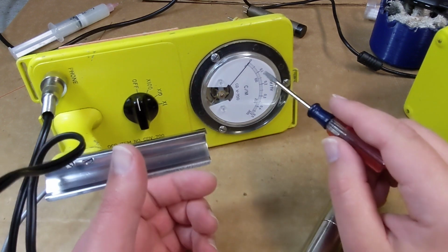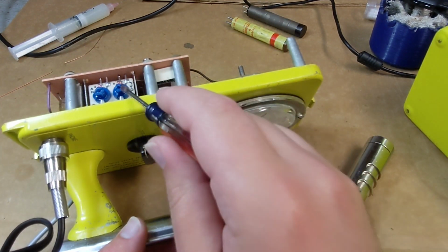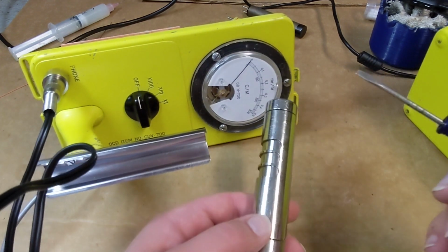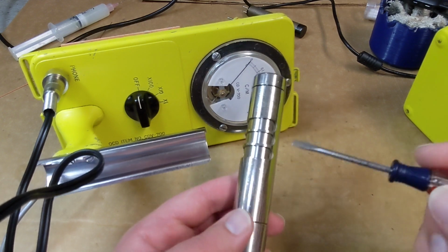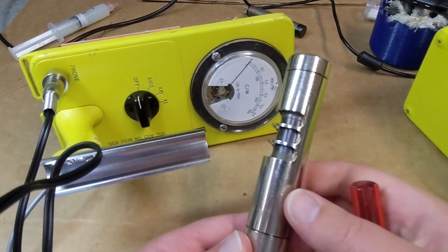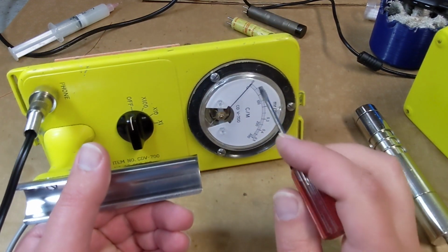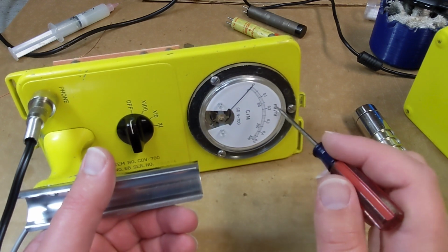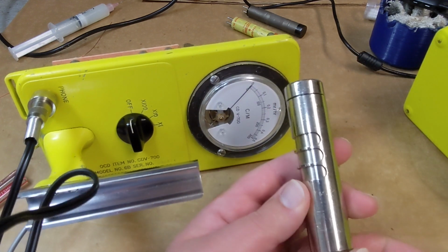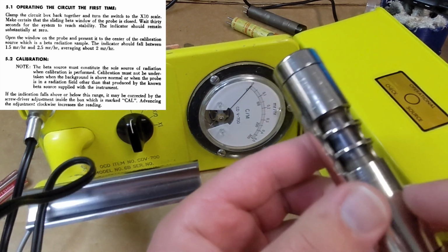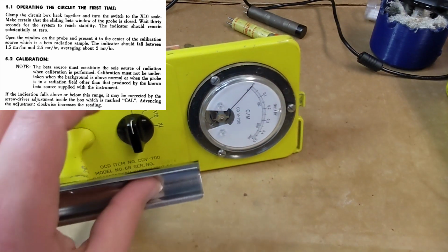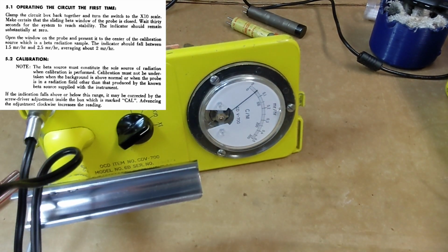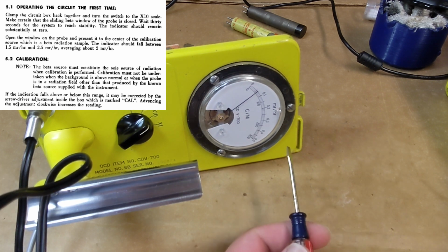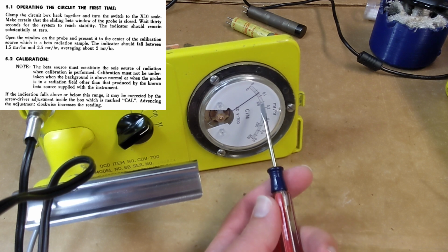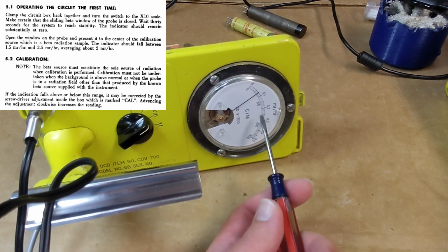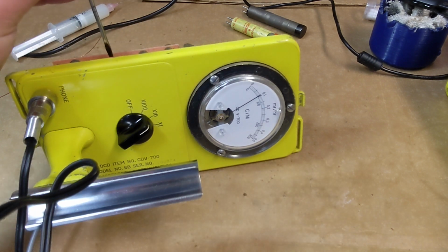Now, the last thing to set is the scaling on this meter here, for which there is another calibration potentiometer right there. Now, this doesn't affect the rate of clicking that comes from the tube, because that's set by the tube geometry and the physics that goes on inside of there. But it does affect the scaling of the meter so that it reads the right value. And what you're supposed to do with that is first open the tube and put it on the check source like that. And then set this to the X10 range. And per the manual, we are supposed to see between 1.5 and 2.5 millirems per hour here, averaging to about 2. So I will try to set that to 2.